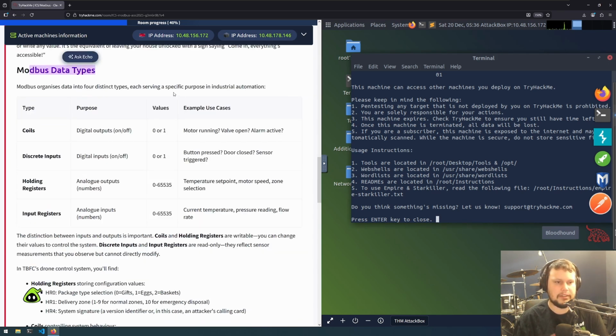So, Modbus data types. There are coils, which are digital outputs where the values are 0 or 1. An example use case is: is the motor running, is the valve open, is the alarm active. Then there are discrete inputs, which are digital inputs of on and off, a value of 0 or 1, and you'd use that for: is the button pressed, is the door closed, is the sensor triggered.